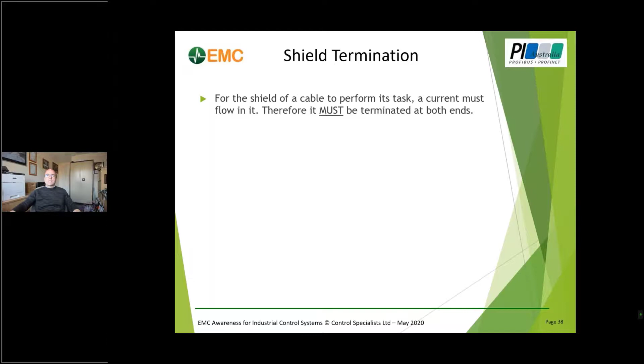Right, it's not always done because of concerns about creating ground loops. Nowadays, with modern day electronics, it's not really an issue as such. It might be on the older style, but certainly with PROFIBUS and PROFINET and that kind of thing, it's not a problem. In the UK, we call it grounding or earthing the shield.